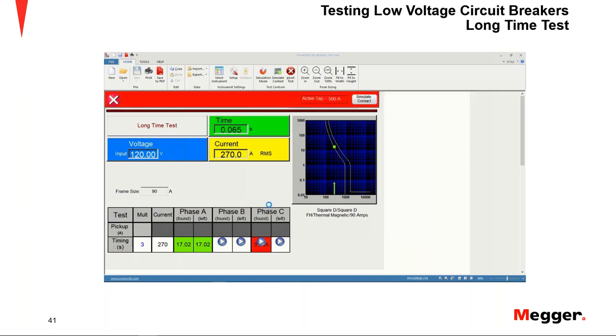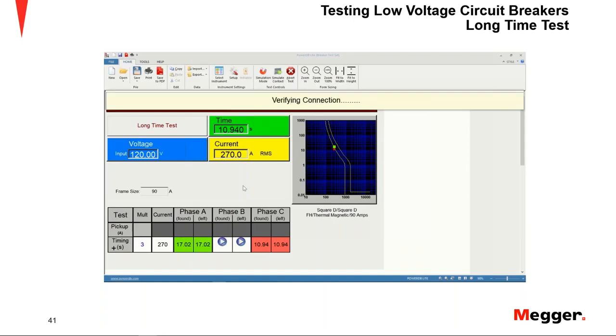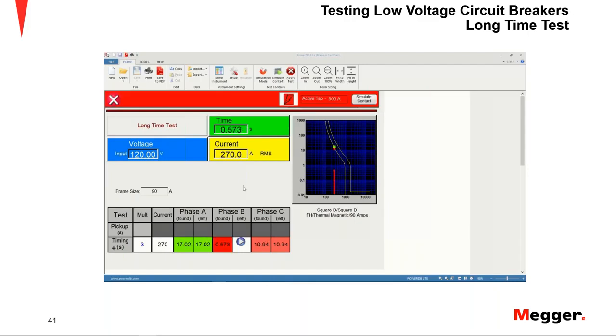So switching to phase C, obviously we have to switch connections to that phase. And again, looking at live results, I have a timer in green in the upper section of the screen. I have a live view of the current as well as the input voltage on the left. In this case, I wanted to show you a failed measurement, how that looks in the graph. And I'm going to leave it like that for a minute, and then switching to phase B. Same process. The unit will always need to determine which tap is in use and calculate the impedance, because we changed connections. So again, showing live results. And again, I'm going to trip this phase when it's within the limits established by the curve. So you notice it turns green when it goes inside the limits.